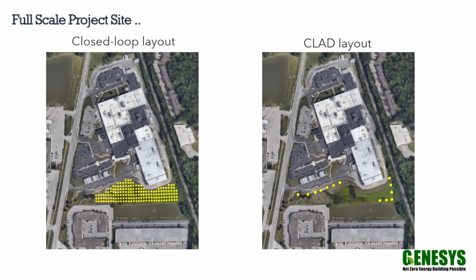To summarize, the building loop can still be a closed loop, meaning the use of glycol is possible. You could still have glycol, methanol, any antifreeze allowed in your region. It's 10 times more efficient than a closed loop, with 90% less area. The prime reason is the type of heat transfer. It's not the typical conductive heat transfer with the ground, but instead you're using water and water to transfer heat against each other, which is a lot more efficient.